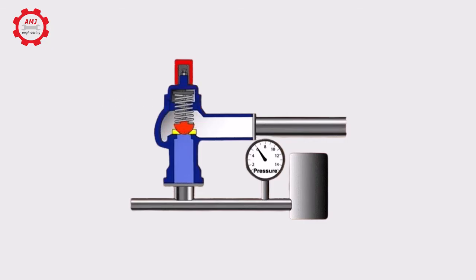This preset force is commonly achieved with an adjusting screw acting on the spring. By turning the screw in or out, the operator compresses or decompresses the spring respectively. The valve can be set to open at any pressure within a desired range.